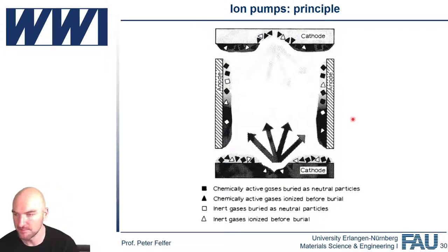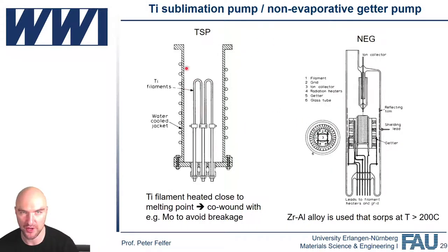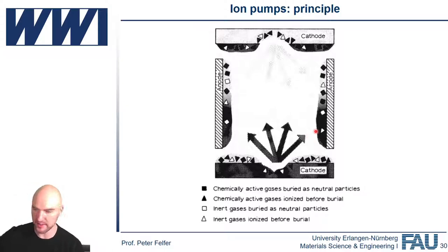In the LEAP systems, what we have are so-called ion getter pumps, IGPs. You've probably seen IGP pump a lot in the user interface there. And ion getter pumps are essentially a dynamical version of creating one of those sorption pumps. So what you do is, you have a gas coming in, and you're trying to ionize those gas atoms and accelerate them towards a cathode. And there they will either get buried or sputter some titanium or whatever material the cathode is made of, and that sputtered material will then be deposited on the anode, and work there as a sorption material.